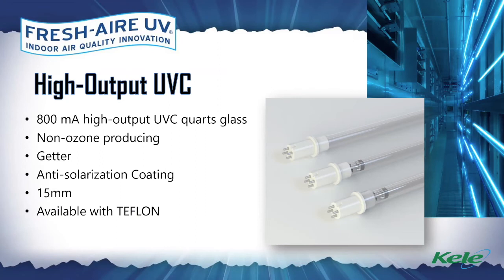We have getters, and there's two rings. You see the rings there in the illustration, which really differentiates our 1 year from our 2 year lamps. Our 2 year lamps use these getters, and these getters absorb the impurities in the gas as the lamp ages. So as the lamp ages, there's pollutants that build up in the gas that ultimately will cause the drop in UV output. By using the getters, which act as filters, they absorb those impurities, making for a much more stable lamp over the course of its 2 year lamp life, those 18,000 hours.